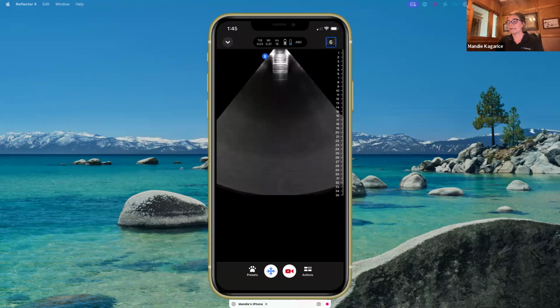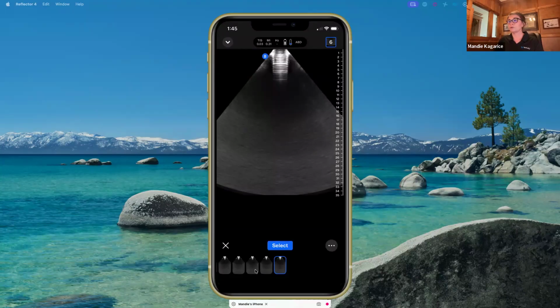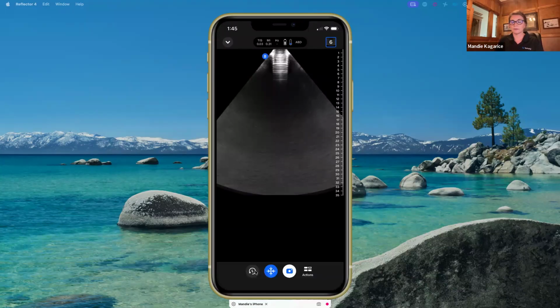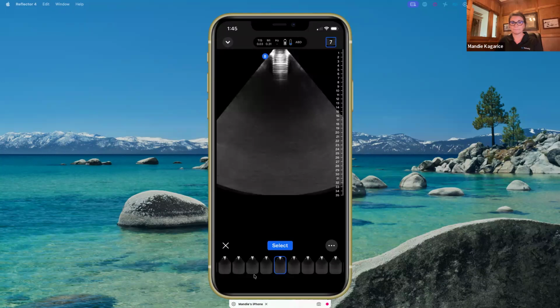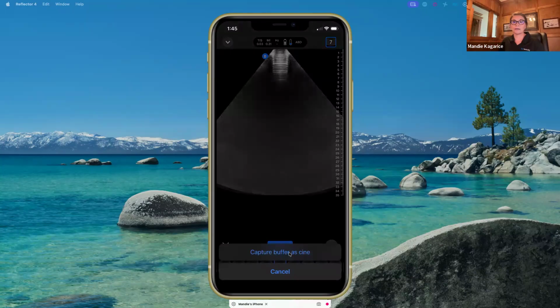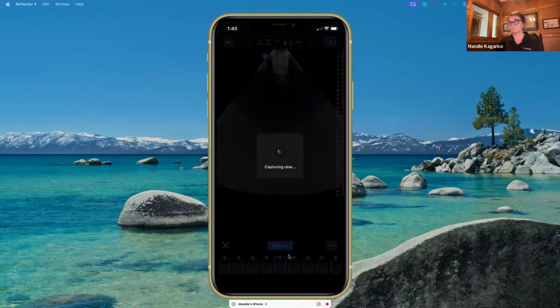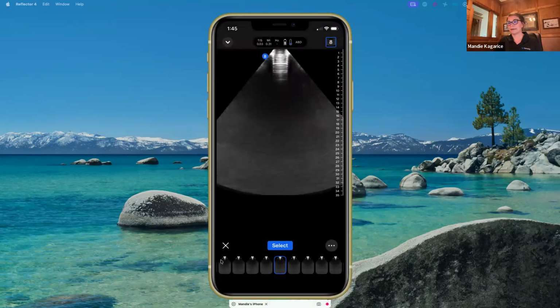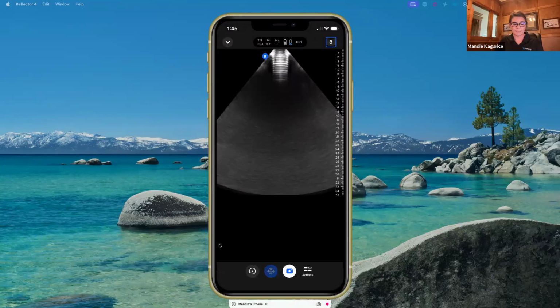Now, if you're scanning along and you hit the freeze button and maybe missed what you were looking to capture, you do have a retrospective time clock when an image is froze. When you click into that, you have a 60-second retrospective clip that you can go through, select out any of those retrospective images, and hit the capture button to capture those. When you're in the retrospective clip, you can also click these 3 little dots, and capture that entire retrospective clip as a cine clip. And that will automatically store there. And then I'm just going to hit the X button and then unfreeze.